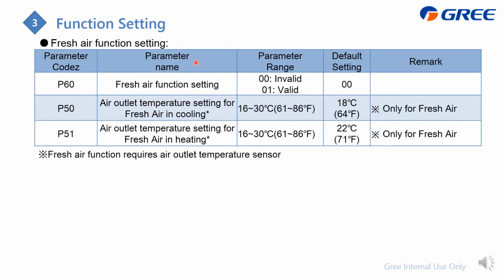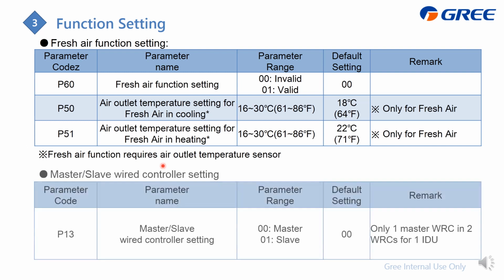As for the fresh air function setting, P60 will make the AHU a fresh air indoor unit, which takes the air outlet as the control target. Then you can set P50 and P51 for the cooling and heating control targets. Also, if you select P60 to be on, you need to connect the fresh air temperature sensor at the AHU air discharge. And selecting the master and slave on the wire controller is at P13.